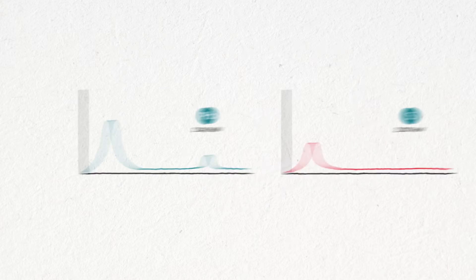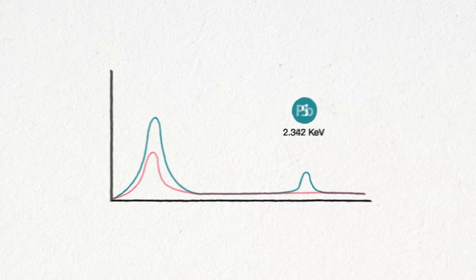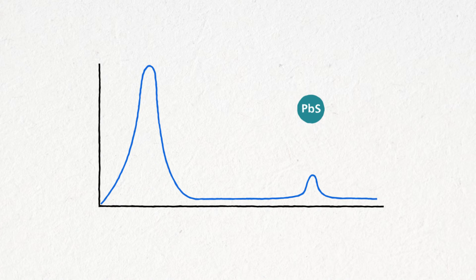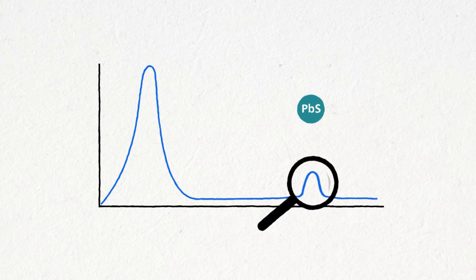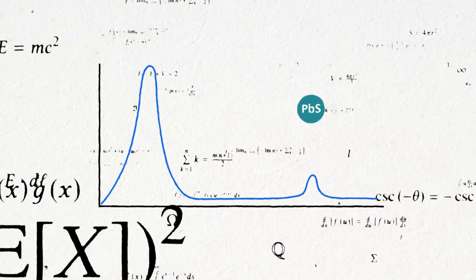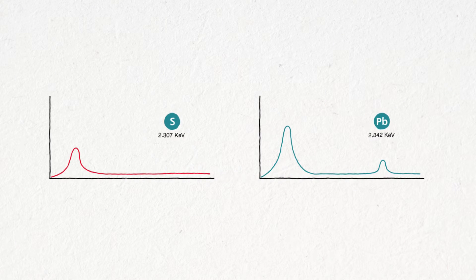The result when these elements are both in the same material is that we will have a peak which is the sum of the two peaks from the individual elements, so it will be taller and we will not be able to see the individual contribution of the two elements. This means that complex mathematical models have to be used to separate these elements, or we can resort to the use of a higher acceleration voltage.